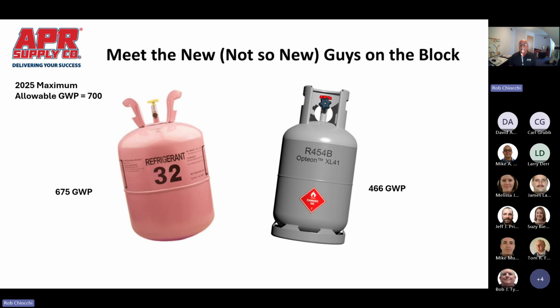Now that is strictly conjecture and rumor. It has by no means been signed into law and has not happened yet, but it is strongly rumored. This is why most unitary manufacturers have chosen R454B as the refrigerant of choice in unitary equipment, air conditioning and heat pumps, and comfort cooling moving forward.